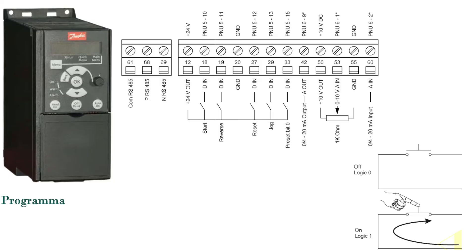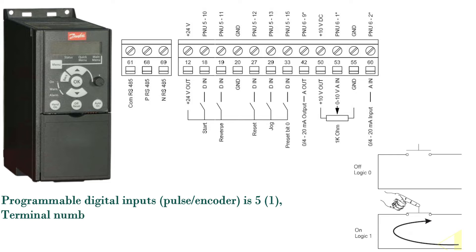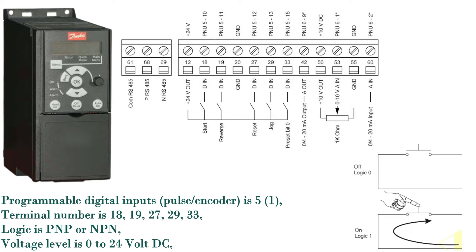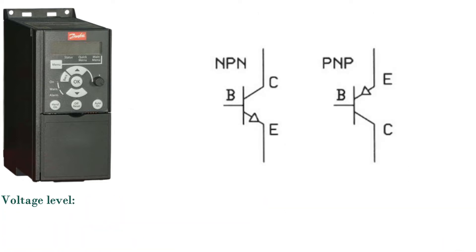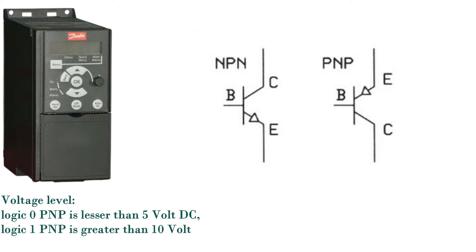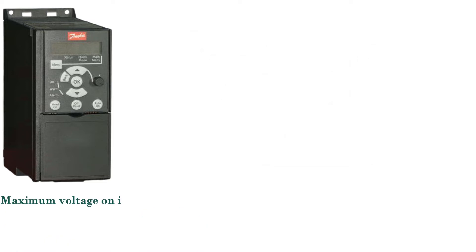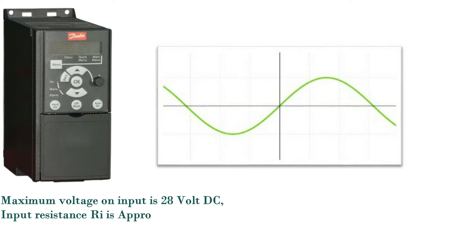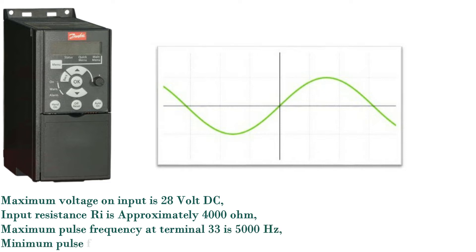Digital inputs: programmable digital inputs plus pulse/encoder is 5+1. Terminal numbers are 18, 19, 27, 29, 33. Logic is PNP or NPN; voltage level is 0 to 24 volt DC. Logic 0 PNP is less than 5 volt DC; logic 1 PNP is greater than 10 volt DC; logic 1 NPN is less than 14 volt DC. Maximum voltage on input is 28 volt DC; input resistance RIN is approximately 4,000 ohm. Maximum pulse frequency at terminal 33 is 5,000 Hz; minimum pulse frequency at terminal 33 is 20 Hz.